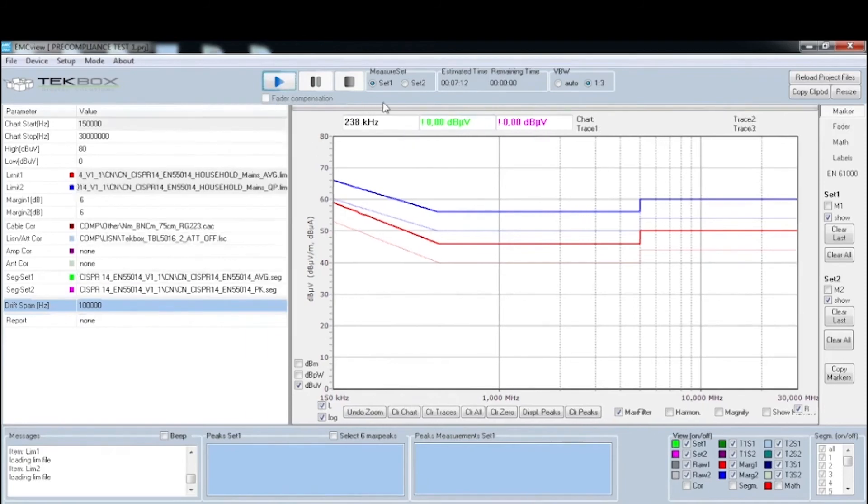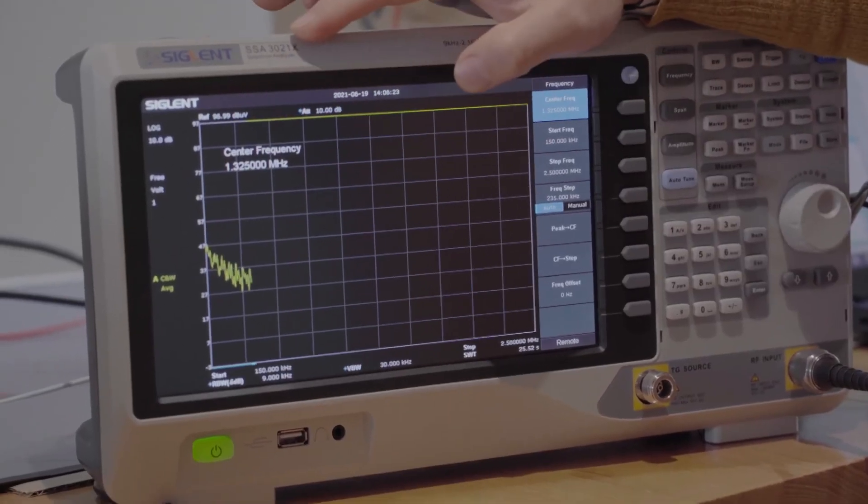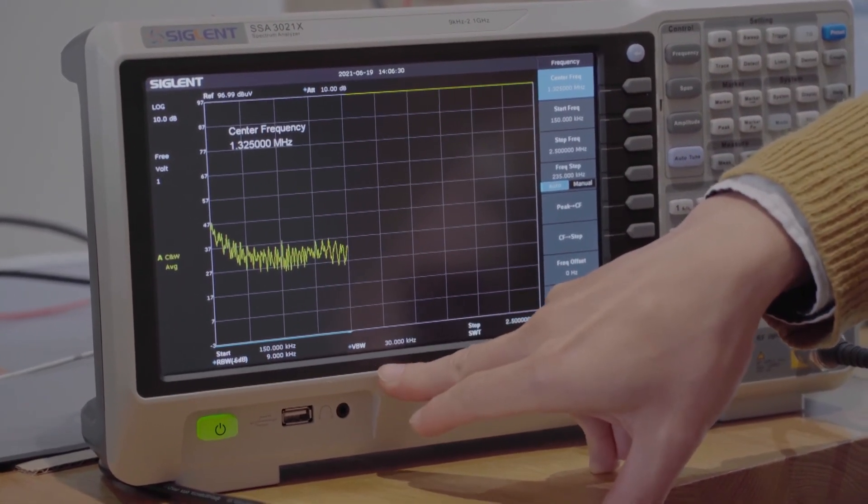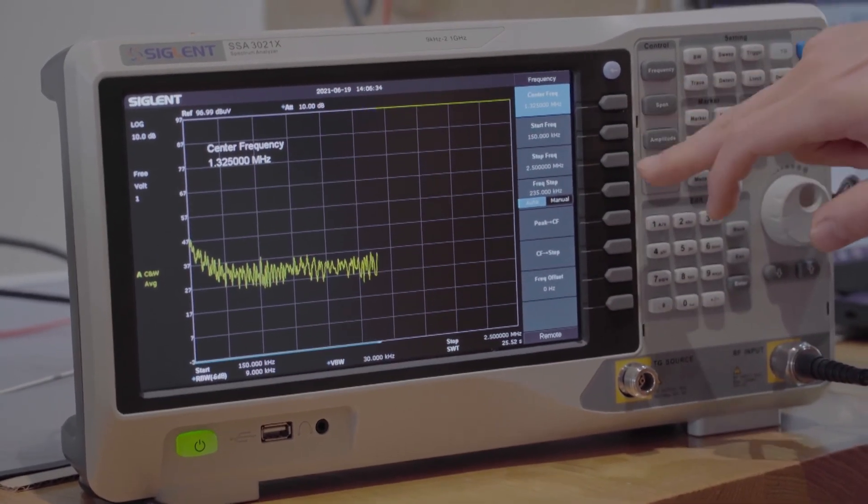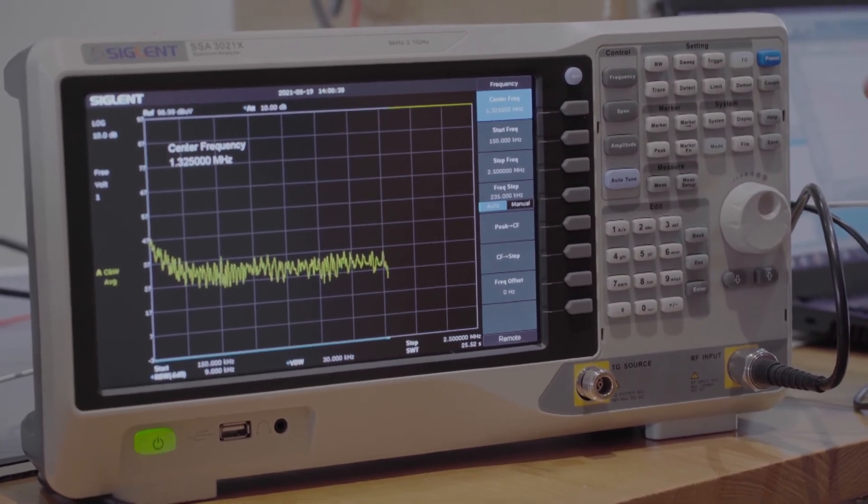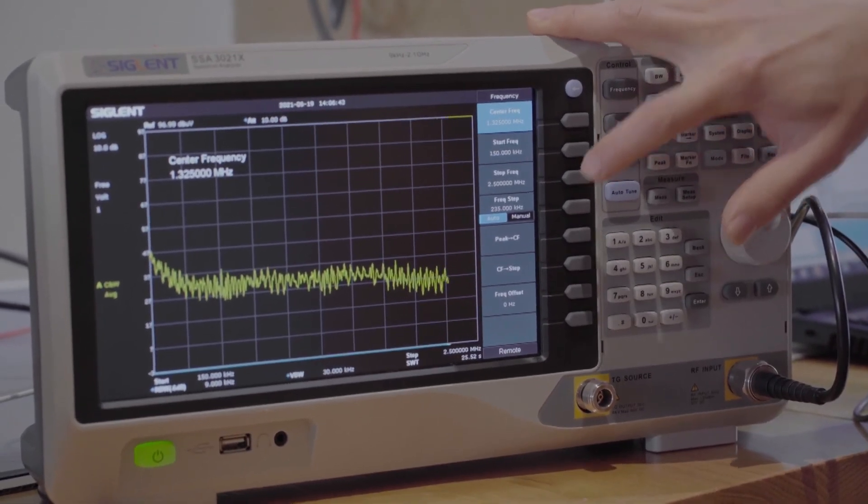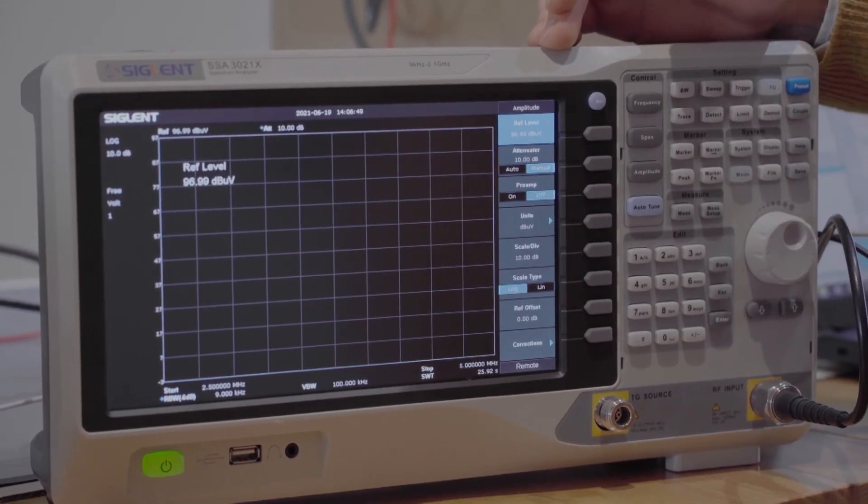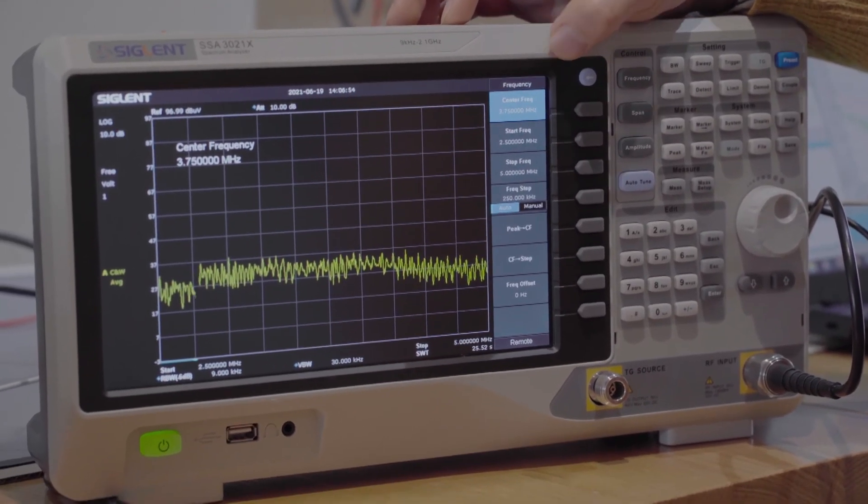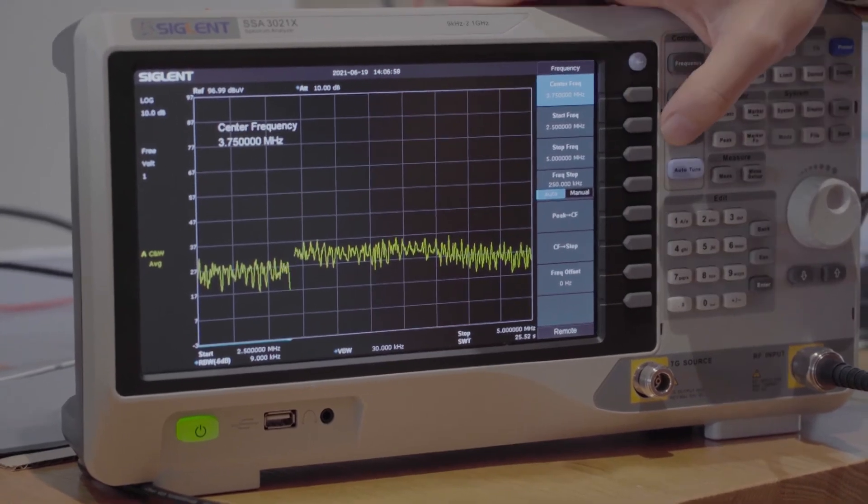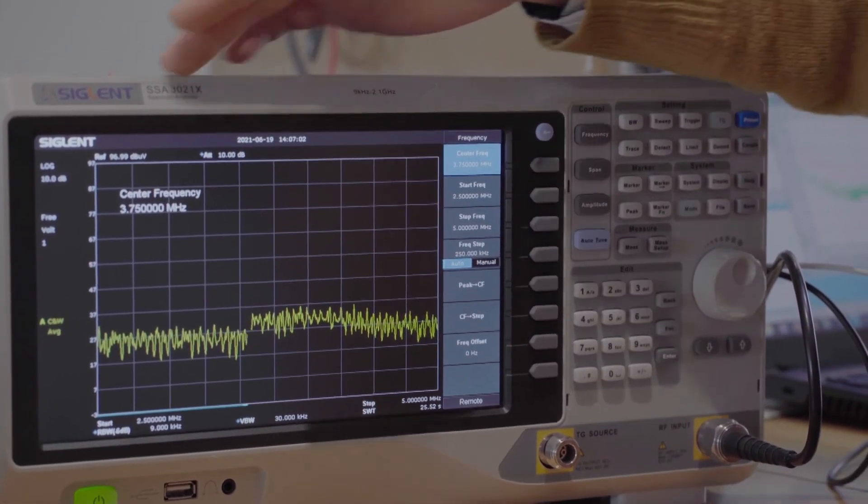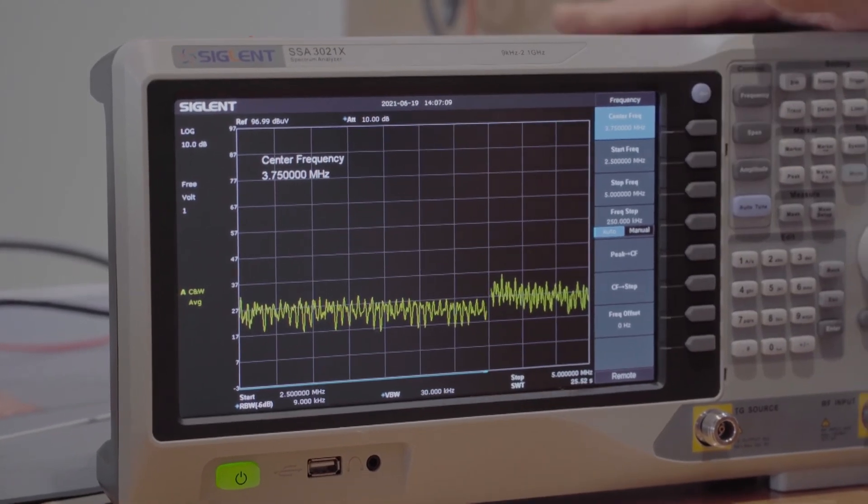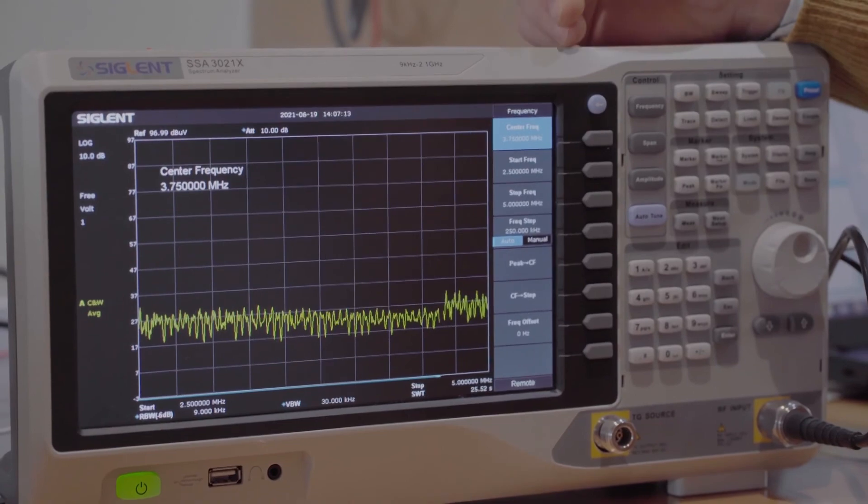Now with all this setup and connected properly to my spectrum analyzer, the next thing I need to do is click start. We're going to click start. As you can see, the software sends commands to my spectrum analyzer. The scanning started now. All the resolution bandwidth, video bandwidth, stop and start frequency has been predefined in the segment file. You can see here, we're doing a frequency step of 235 kilohertz scan. That's the first segment scanning finished. Now we're starting from 2.5 megahertz and will stop at 5 megahertz. You can see all the values are predefined in the setup file in EMC View. Very easy, we just wait until the scan of each segment is finished.